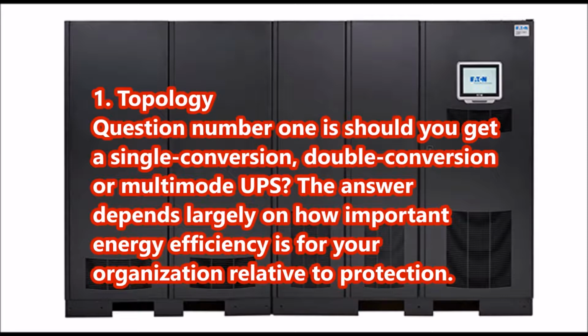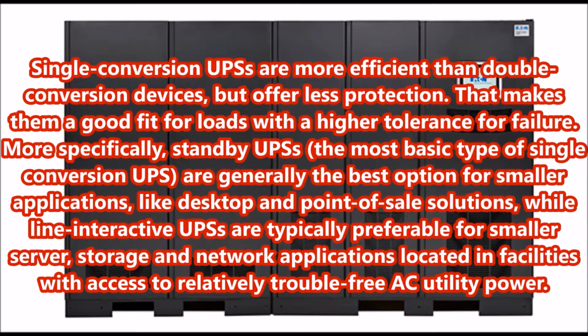The answer depends largely on how important energy efficiency is for your organization relative to protection. Single conversion UPSs are more efficient than double conversion devices, but offer less protection. That makes them a good fit for loads with a higher tolerance for failure. More specifically, standby UPSs, the most basic type of single conversion UPS, are generally the best option for smaller applications, like desktop and point-of-sale solutions, while line interactive UPSs are typically preferable for smaller server, storage and network applications located in facilities with access to relatively trouble-free AC utility power.